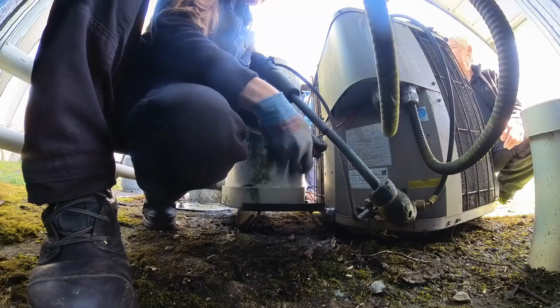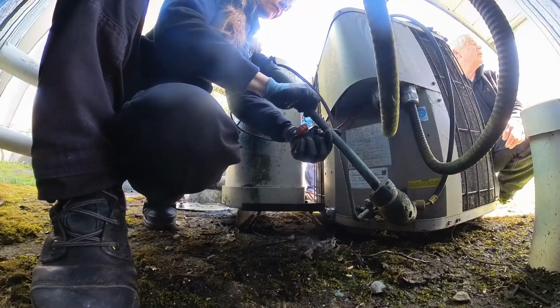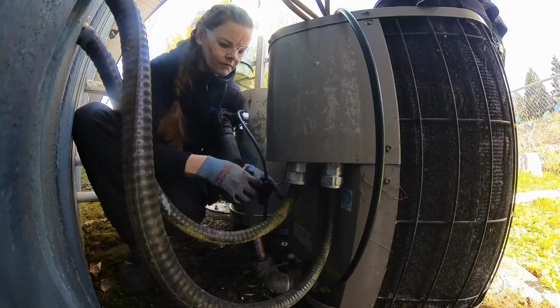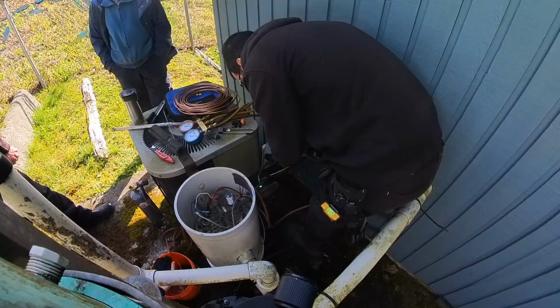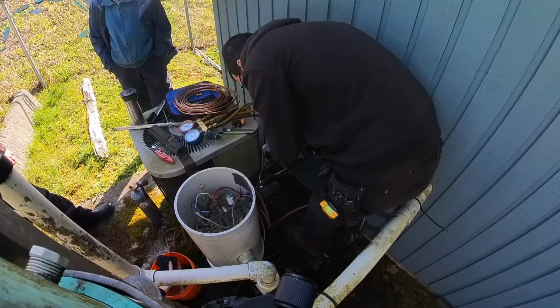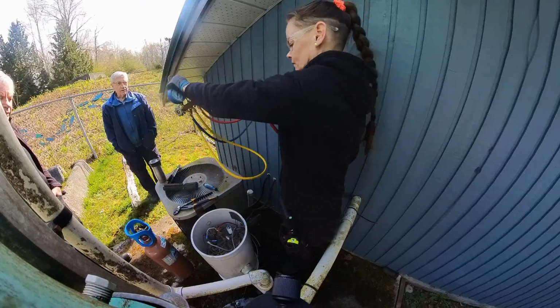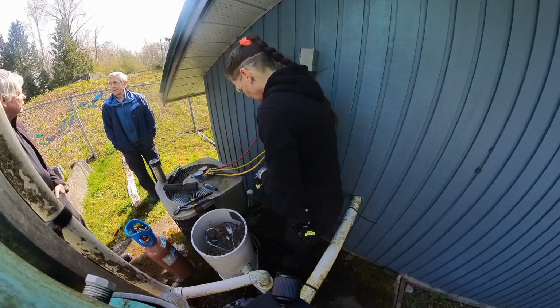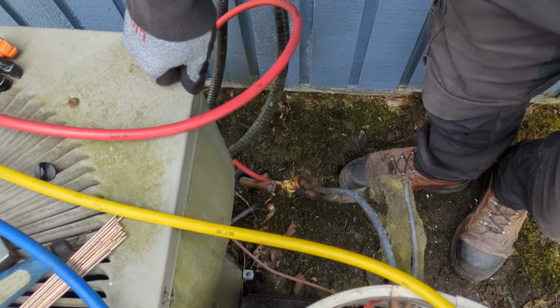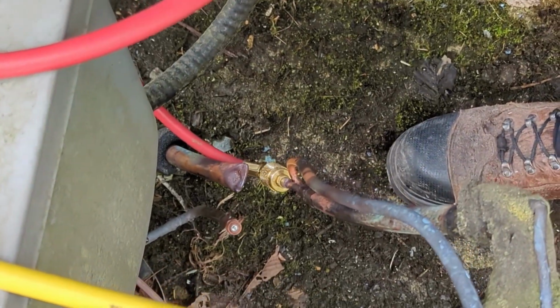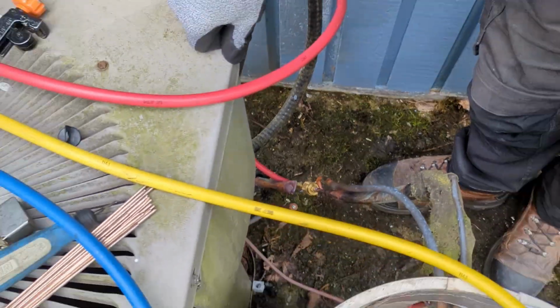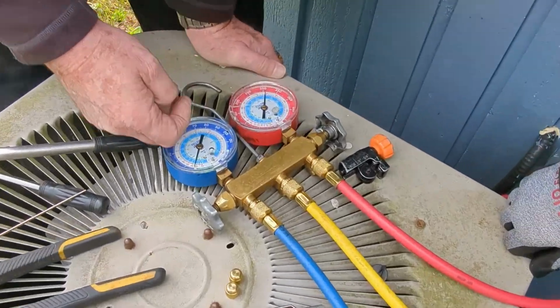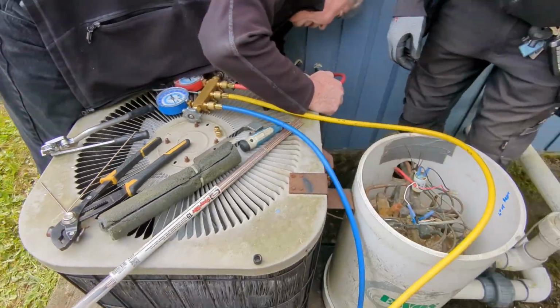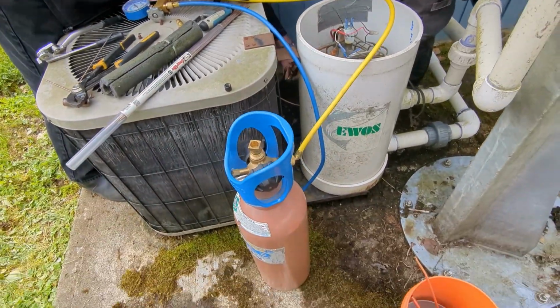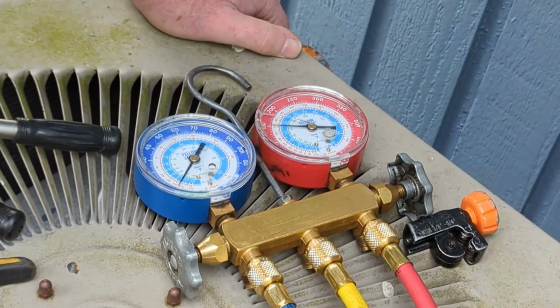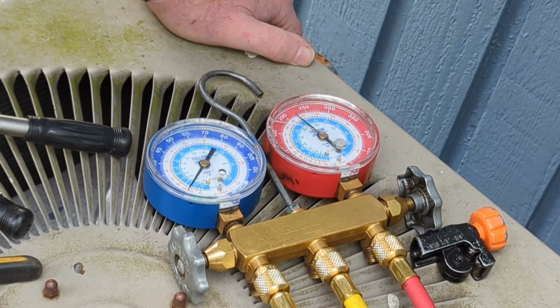With all of the refrigerant out of the system, I can cut both the suction line and the liquid line. And Trevor's brazing in an access fitting on each of them. Now it's time to pressurize each of these systems with our fancy little access ports here. We're going to use nitrogen and we're going to take it up to about 300 psi. And we're going to leave both of them over the weekend. Then we will return the following week to see if we had dropped pressure at all.